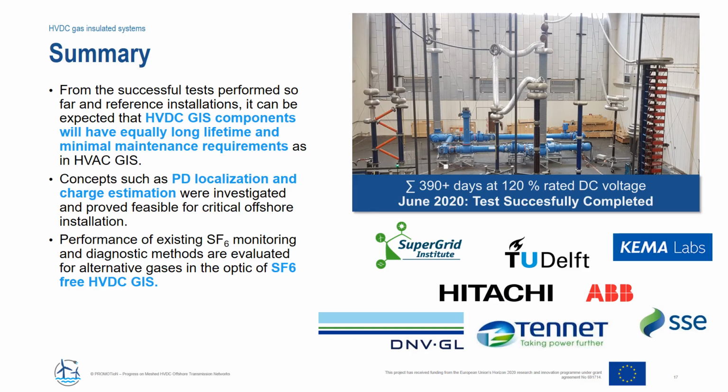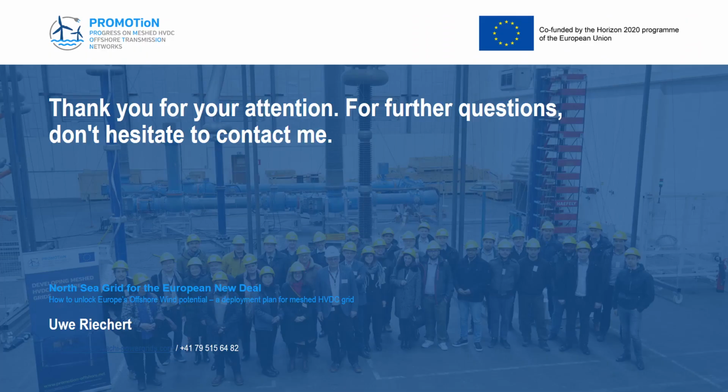Concepts such as PD localization and charge estimation were investigated and proved feasible for critical offshore installations. Performance of existing SF6 monitoring and diagnostic methods was evaluated for alternative gases in the light of future SF6-free HVDC GIS. Thank you very much for your attention.